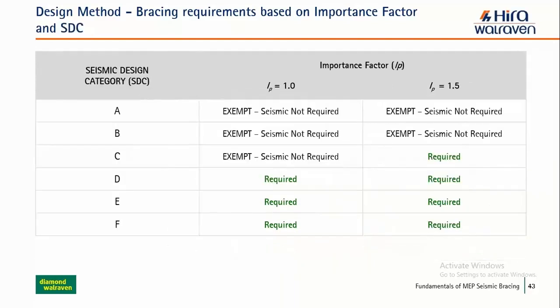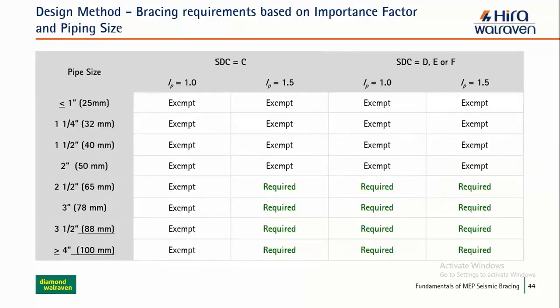So as discussed, based on seismic design category and life safety versus non-life safety services, now we're adding one more item: pipe sizes. If you're dealing with firefighting pipes or other pipes for both life safety and non-life safety, and you have seismic design category C with pipe size 65mm, it could be exempt from 1.0 and required only for life safety.